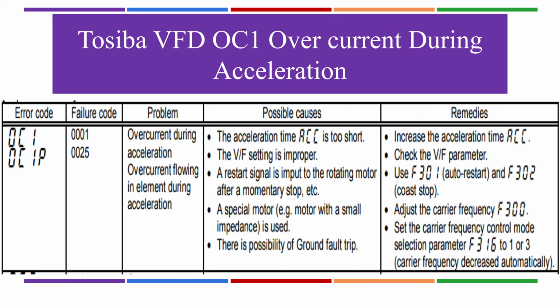Check the V/F parameter. Use F301 to restart, F302 to coast stop. Coast stop is an immediate stop. Adjust the carrier frequency at F300, and set the carrier frequency control parameter F316 to 1 or 3. Okay. So normally this error occurs when the acceleration time is very short.